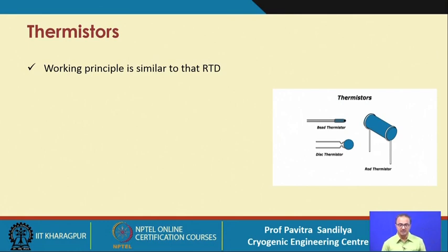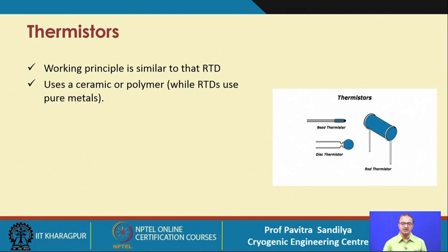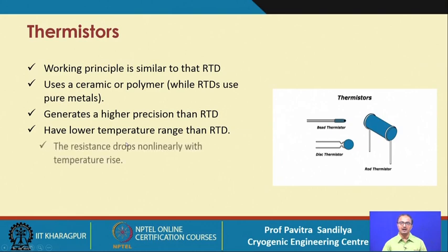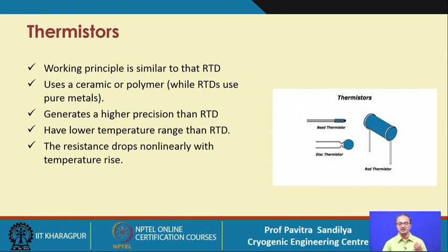The thermistor is similar in principle to the RTD, but uses ceramic or polymeric material rather than metallic material. It gives very high precision and works well, but its operating temperature span is lower than RTDs. The resistance drops non-linearly with temperature rise — unlike the RTD — and we always prefer devices with as linear a response as possible. The RTD is best in this regard, giving almost linear resistance variation, so only two calibration points are needed, whereas non-linear devices require more standards.